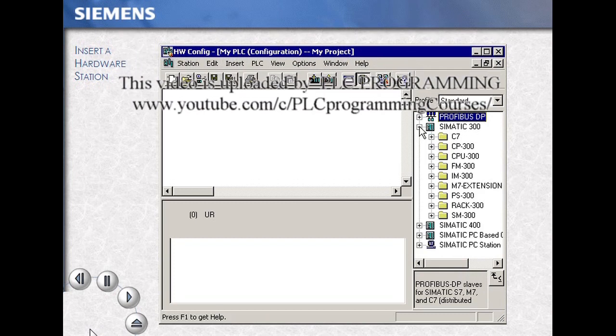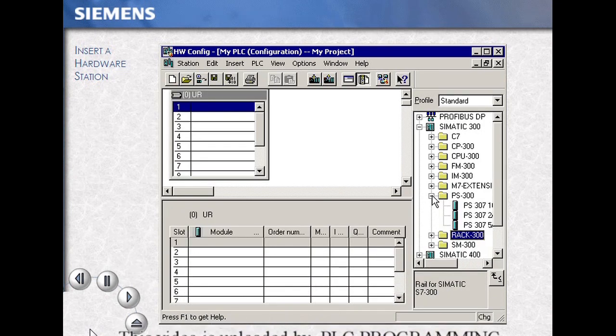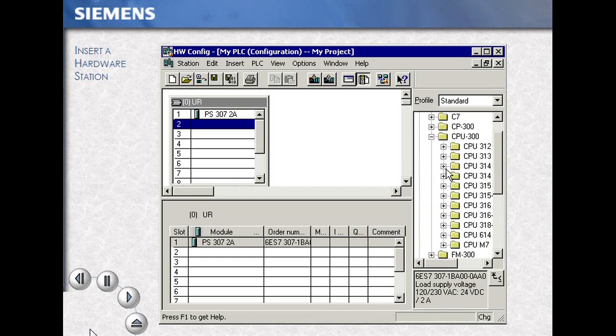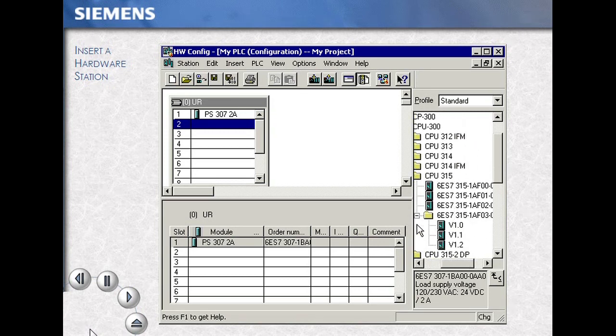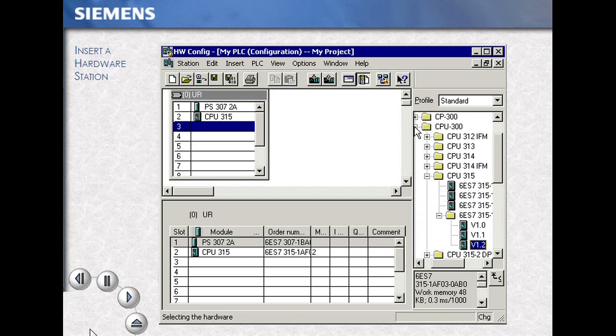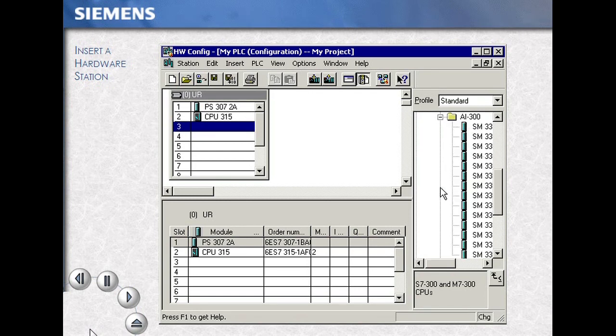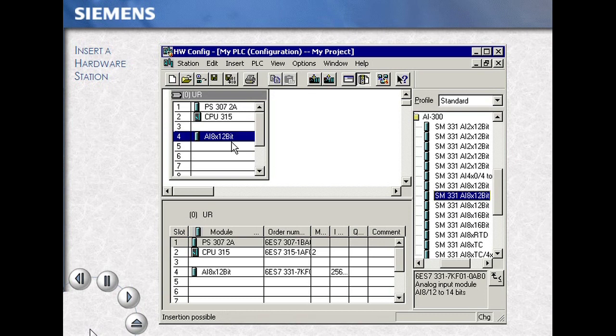Open your station and double-click on the hardware icon. This opens the hardware configuration tool. Select the catalog icon to access the components catalog. Expanding SIMATIC 300 Station, we begin by selecting a rail, then a power supply. A double-click from the catalog places the module in its specified slot. As we navigate through the catalog, you can see a variety of different components — Digital modules, Signal modules, and Analog modules can all be selected. This example is choosing an Analog Input module. Note: as the module is dropped in the rack, the addressing is automatic. Save and compile your work.